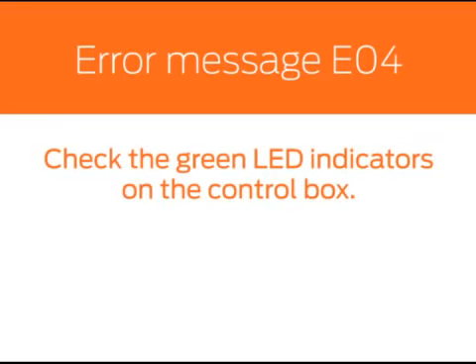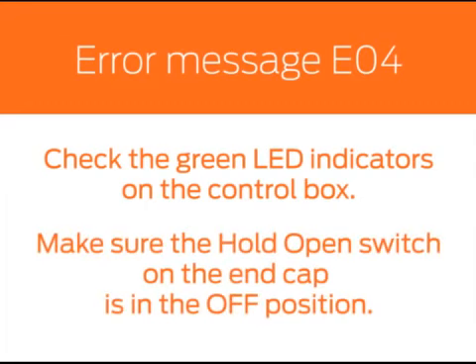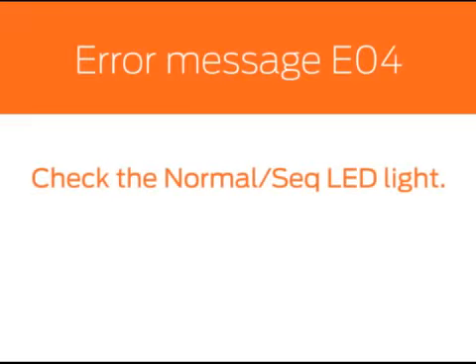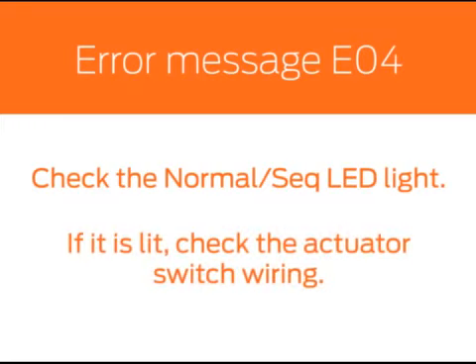When an E04 message appears, this indicates the operator is in continuous activation when the unit is turned on or when you exit programming mode. Check the green LED indicators on the control box. If the Hold Open Alt Action LED is lit, check the Hold Open switch on the end cap. Make sure this switch is in the off position. Another possible cause of the E04 message is an error with the actuator switch. If you see the normal SEQ LED lit, check the actuator switch to see if it is miswired or stuck.